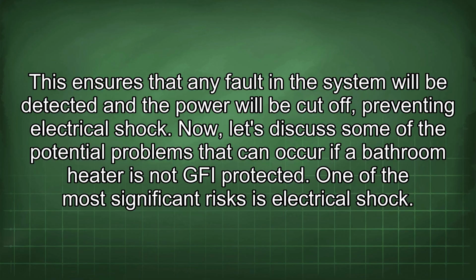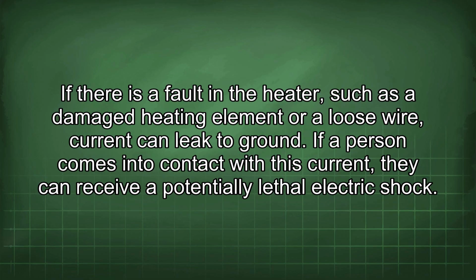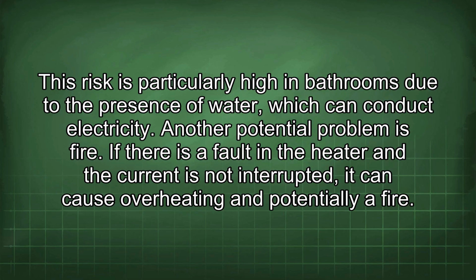Now, let's discuss some of the potential problems that can occur if a bathroom heater is not GFI protected. One of the most significant risks is electrical shock. If there is a fault in the heater, such as a damaged heating element or a loose wire, current can leak to ground. If a person comes into contact with this current, they can receive a potentially lethal electric shock. This risk is particularly high in bathrooms due to the presence of water, which can conduct electricity.